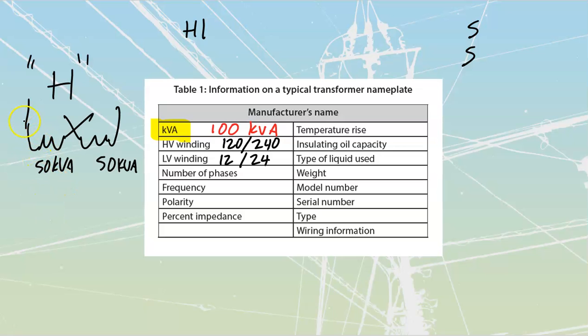So each of these sections would be good for 120 volts over here in the high voltage. Low voltage acts the same. Once again, if we get split, the lower value is what I would have for an individual coil inside of that transformer. The higher value, the second one, would refer to what it would look like if I were to series those two coils together.